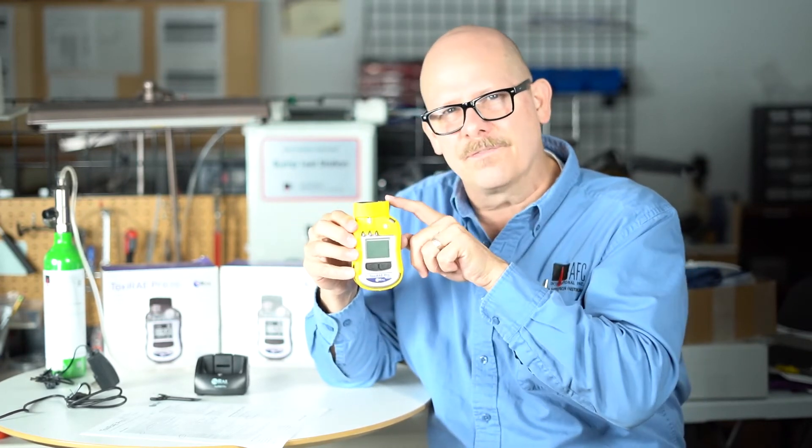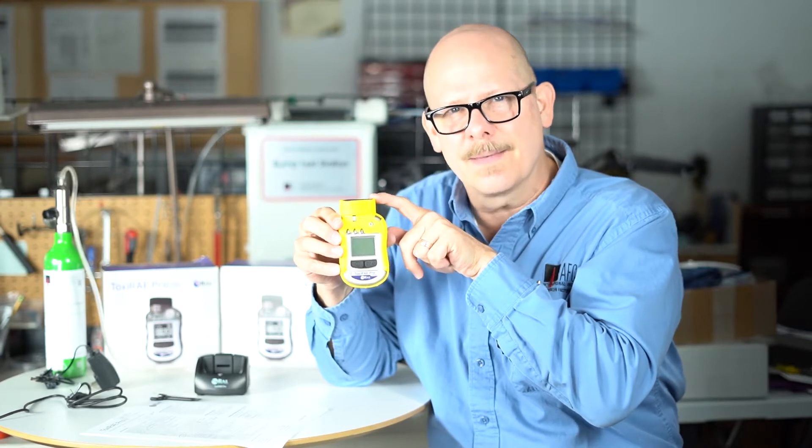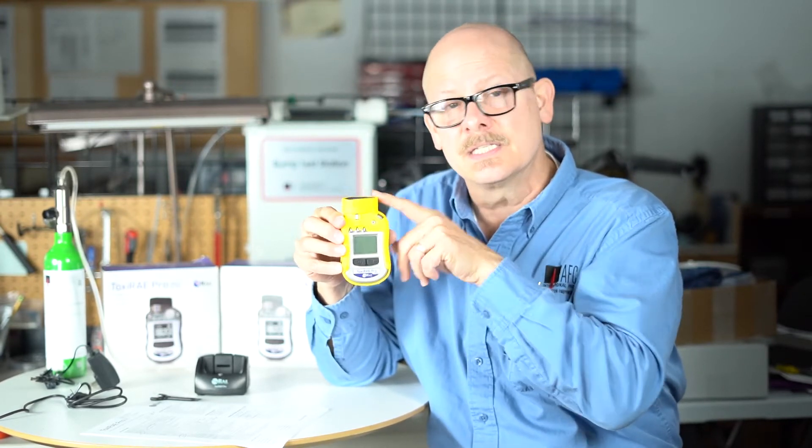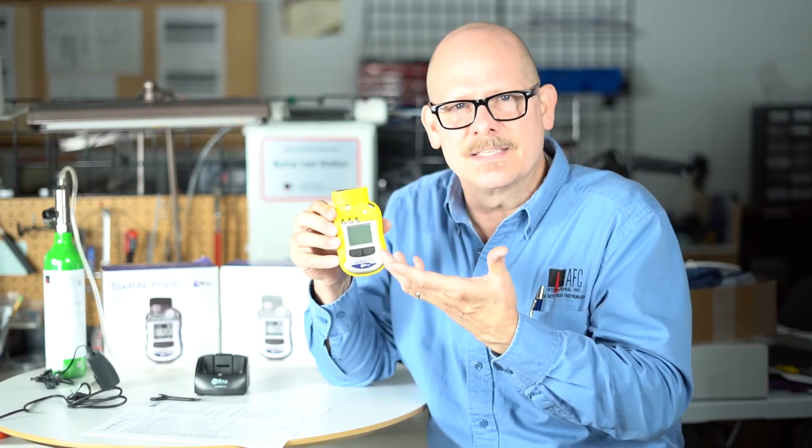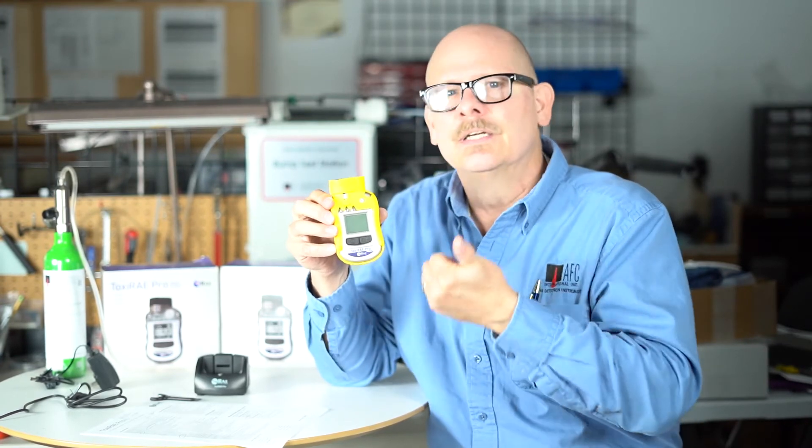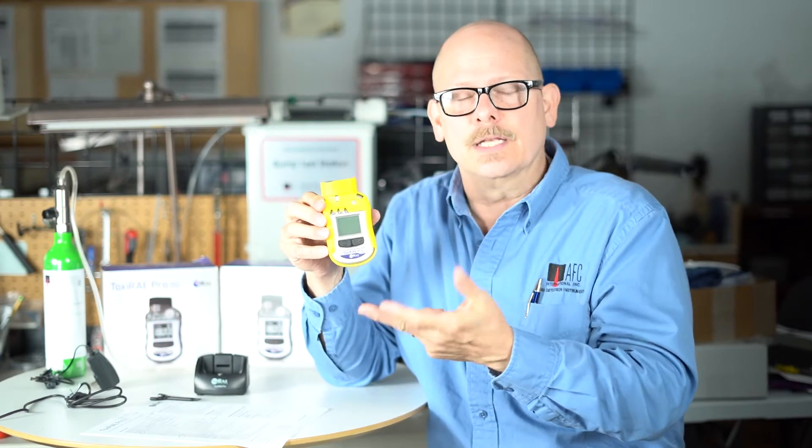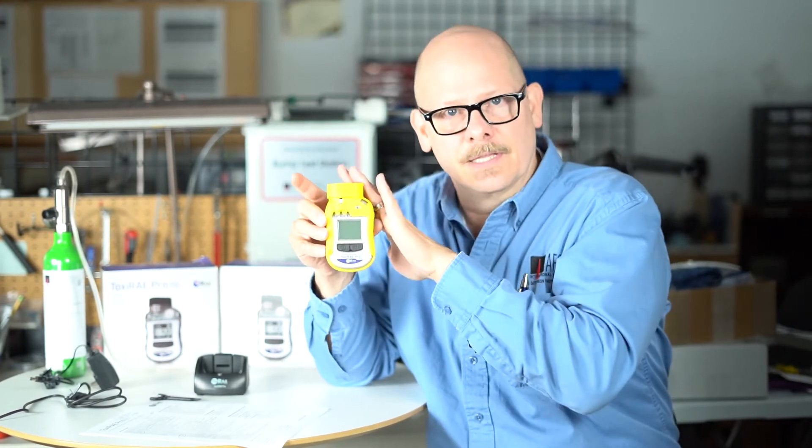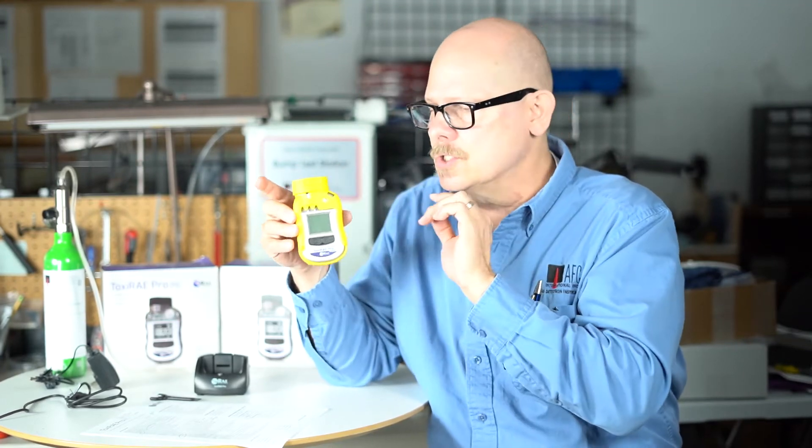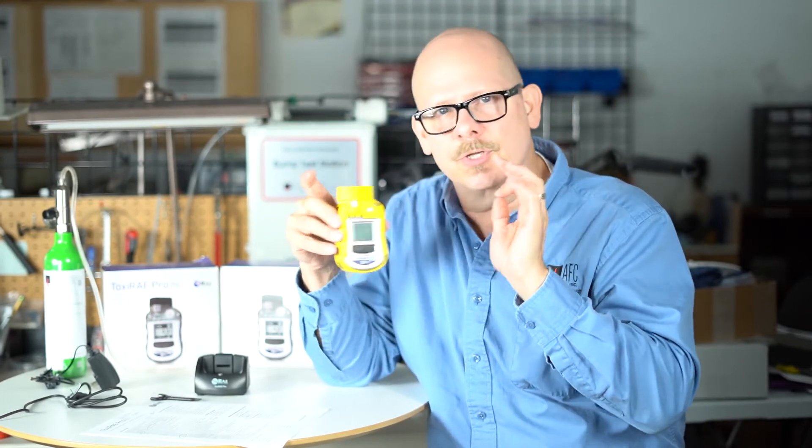PIDs work off the ionization potentials of chemicals. If our lamp energy is only 10.6, we can't ionize gases and vapors or chemicals above that 10.6. So that would be like methanol, formaldehyde, methylene chloride. We can't see those because those ionization potentials are higher than the lamp availability for the ToxiRAE Pro.